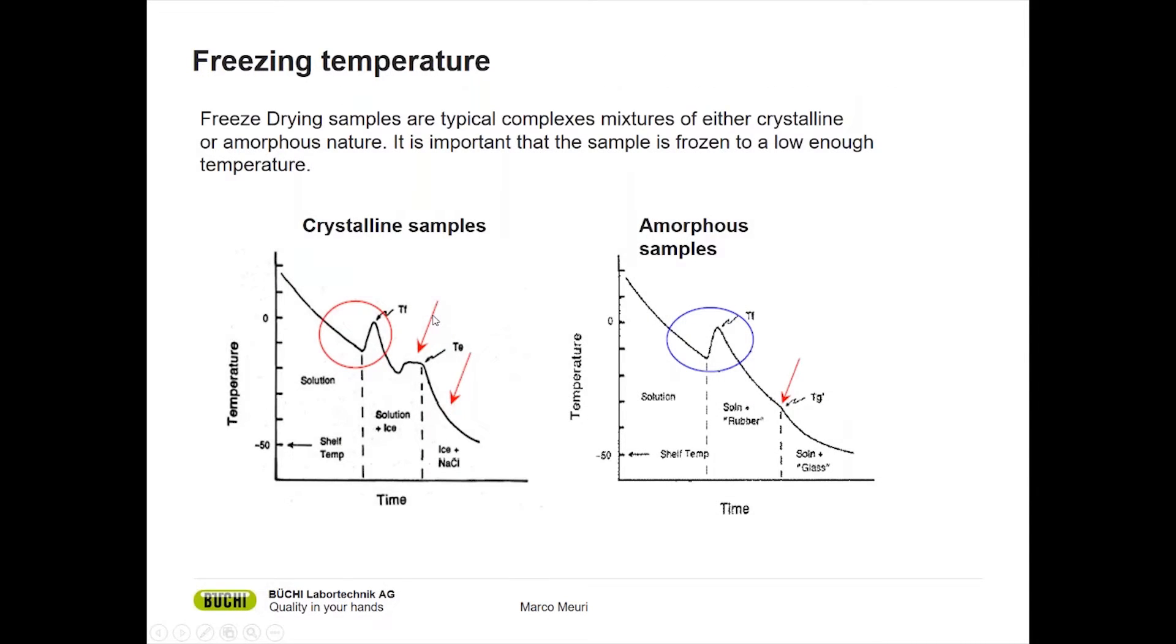In general, when we talk about freeze drying, freezing the sample is very important and the temperature to freeze a sample is extremely important for the freeze drying process. Freeze drying samples are typically complex mixtures, either crystalline or amorphous, and they're not so easily frozen as you would expect.